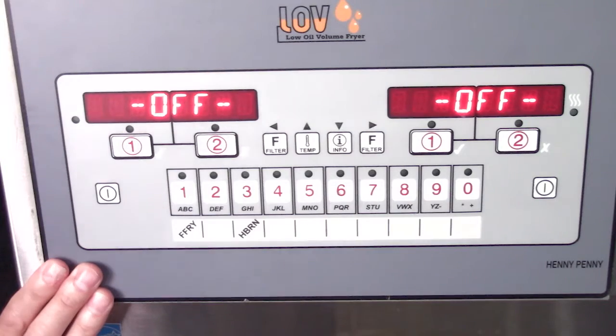Now let's take a look at the control board, and we'll start seeing how we can troubleshoot if that's not the issue. 1, we have the correct amount of oil in the fry vat. 2, if we're looking at the atmospheric equalization hole, it's not clogged up. So now we want to start taking a look at what is going on component-wise as to why our main gas valve is not coming on. I'm going to go ahead and explain it a little bit before I turn it on.